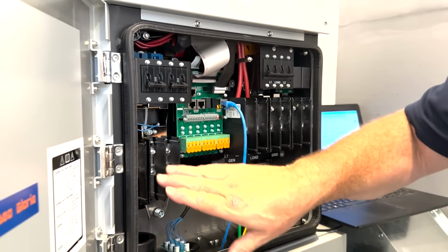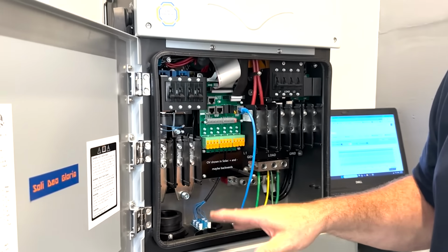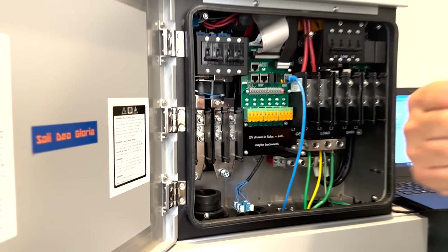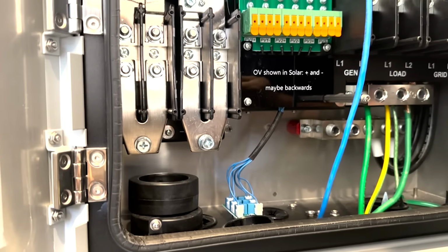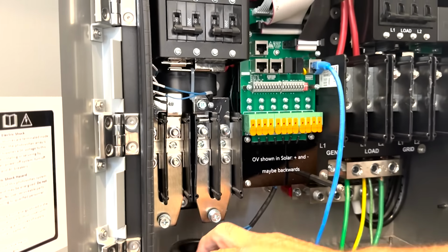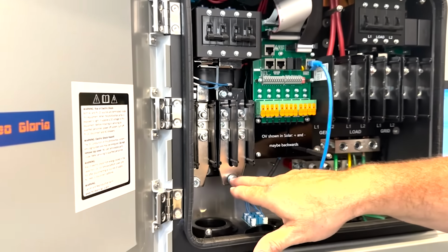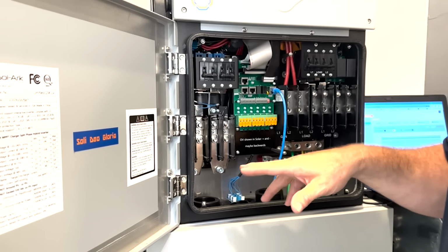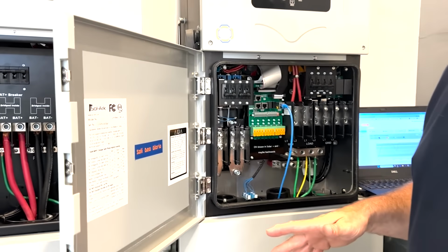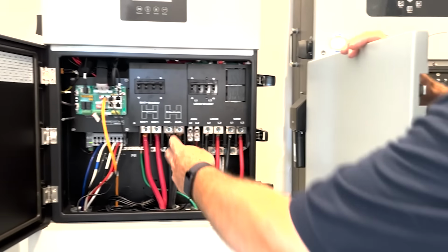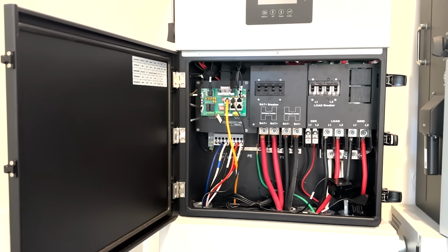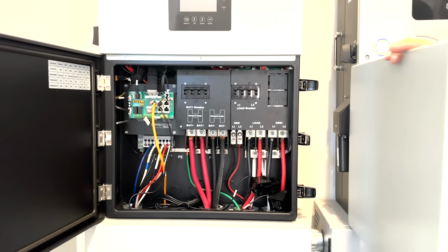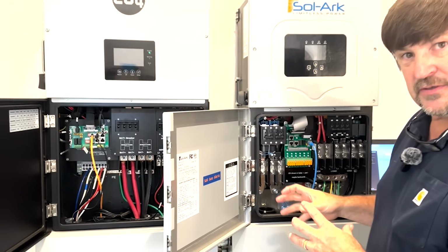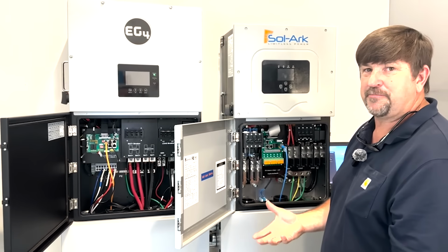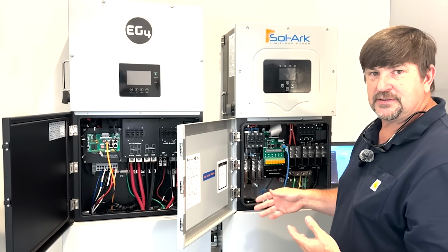On the Sol-Ark battery, I'm always landing 4-aught cable with lugged cables, either pre-lugged by a manufacturer or we do them ourselves with mechanical lugs. And then we have these branch connectors. A lot of times, like we just did a job with 700 feet of battery cable - if I had to do that otherwise, I would have 1,400 feet of battery cable. So that's an example of saving some money, less wire, less space, but even better performance.